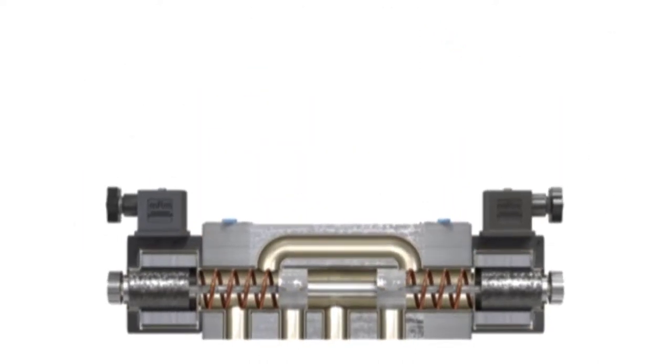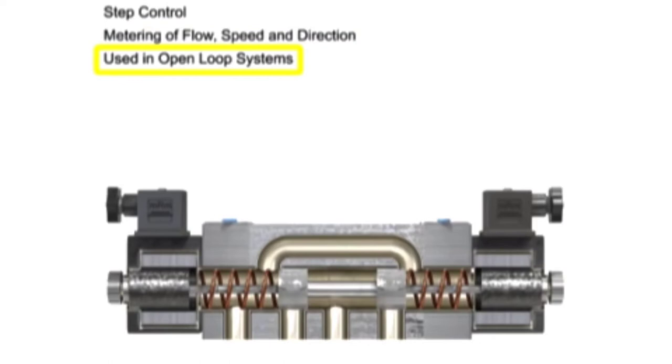Proportional control valves allow for variable control of spool movement, which allows more step control and metering of flow, speed, and direction. Most valves of this design are used in open-loop systems to smoothly accelerate and or decelerate an actuator or cylinder.